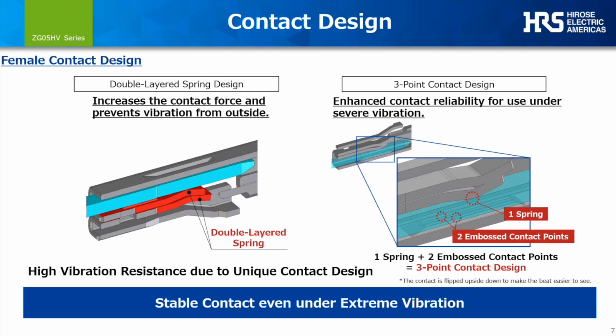Moving on to the contact design: this connector is suitable for high vibration environments due to the combination of the double layered spring design plus the 3-point contact design. Here you have the double spring layer design, with two springs pushing force up on the male pin, and the 3-point contact design which has 2 embossments and a spring contact. The 2 embossments and spring contacts hold the male pin firmly, while the double layer spring design increases the contact force on the male pin to counteract any external vibration. This results in a robust connection point under extreme vibration, so for applications with high vibrating environments, this connector is perfectly suitable.